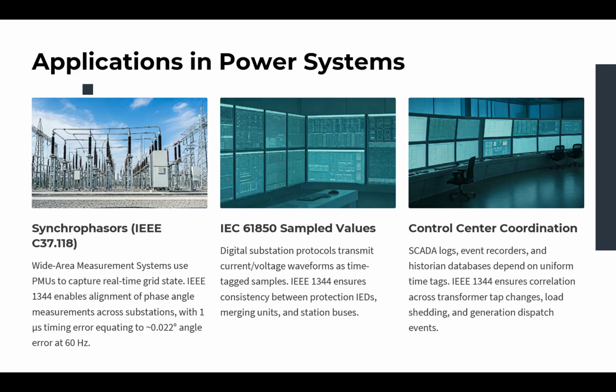Let's examine three core applications. One is synchrophasor, which uses IEEE C37.118. The PMUs, the phasor measurement units, measure the magnitude and phase angle of the voltage or current at a certain instant, usually at 30 to 120 samples per second. These measurements are time-tagged and then transmitted to a central location, which could be a control center or a phasor data concentrator. The standard defines synchrophasor performance in IEEE C37.118, and it explicitly requires synchronization error to be less than 1 microsecond.